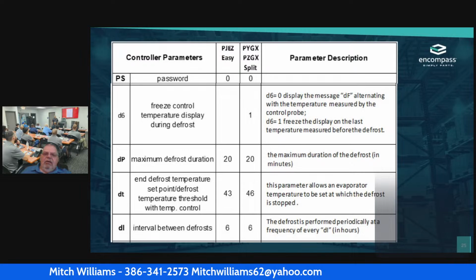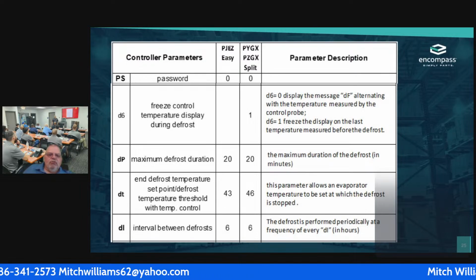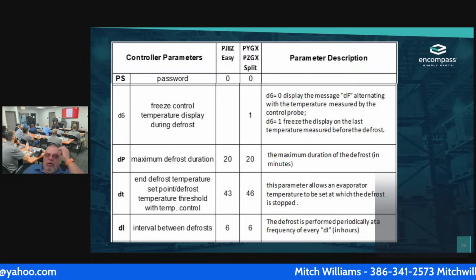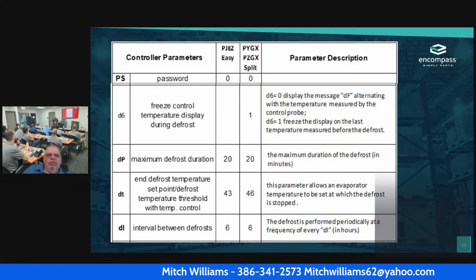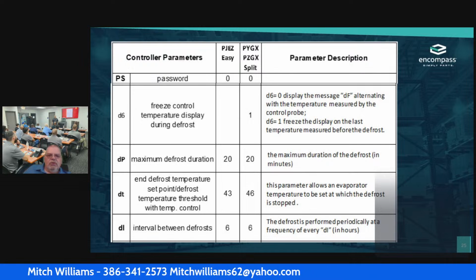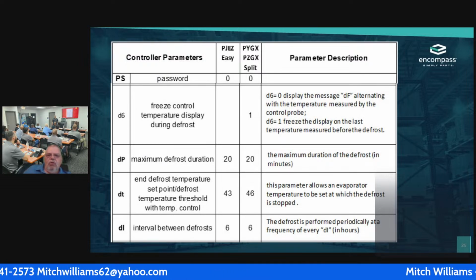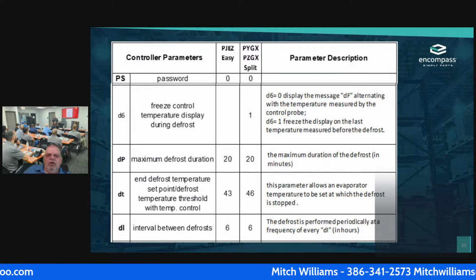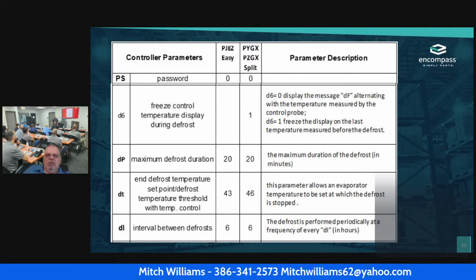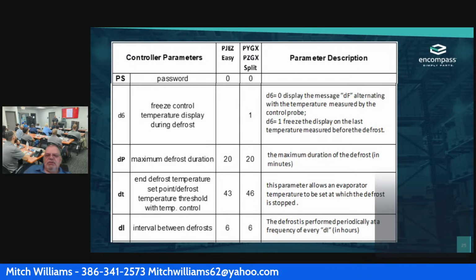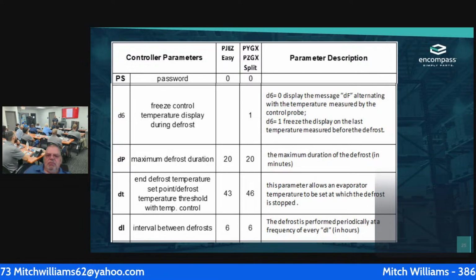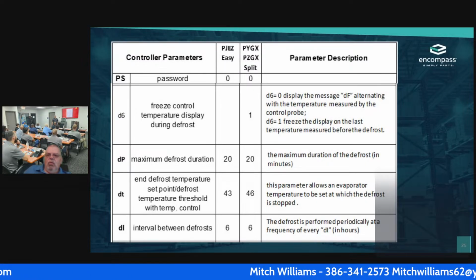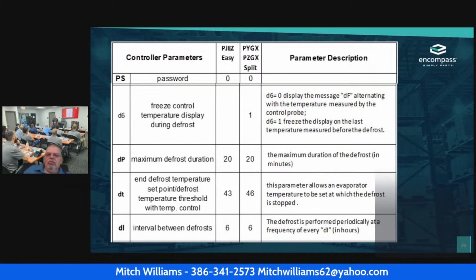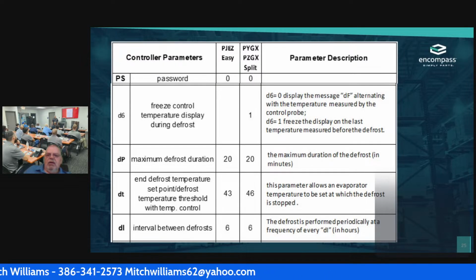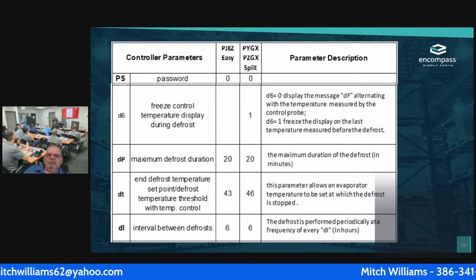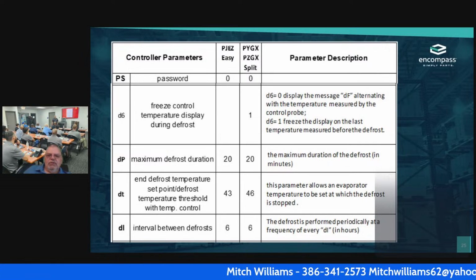Okay. Now, if I have a D6, this is my freeze control temp. The D6 is whenever I'm on that controller and I scroll through. That gives me the temperature control, the freeze control temperature during the defrost. That tells me what temperature is inside the unit while it's in defrost. So 0, the message DF alternating with the temperature measured by the control probe. If I change it to a 1, that's the freeze on the display. Freeze on the display on the last temperature measured before the defrost. So I can either turn it to a 0 or a 1.